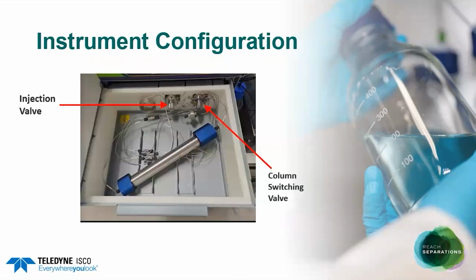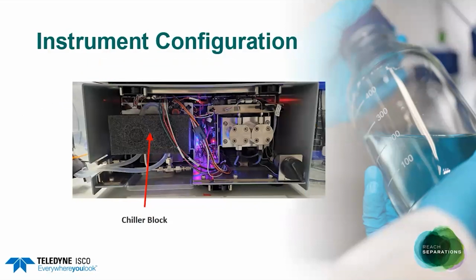If we look inside the column oven drawer, we have a 6-position column switching valve, and also the injection system is housed in here. Keep the temperature of all those components nice and stable, as I mentioned earlier. Down at the bottom, we have the two main mobile phase pumps, and also hiding around the back is the makeup pump. The left-hand pump is a CO2 pump, which requires the cooling block on the heads of the pump. These particular pumps are SSI pumps, which we do ourselves have on other systems in our labs, and we have actually found these pumps to be very robust pumps indeed.